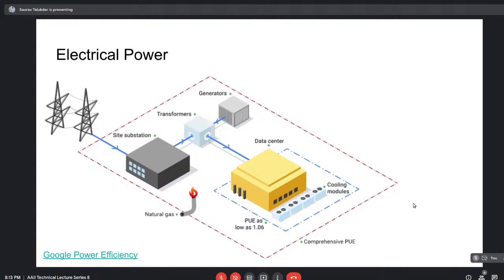And the reason I bring this up is that in our world there is a metric for energy efficiency, which we call PUE. PUE is essentially the ratio of the total data center power consumption divided by the consumption only by the servers. When I say total power consumption, it means power consumption by the servers plus all the cooling infrastructure. If this ratio is much higher than 1, it means we are spending a lot of energy also to cool the computers.